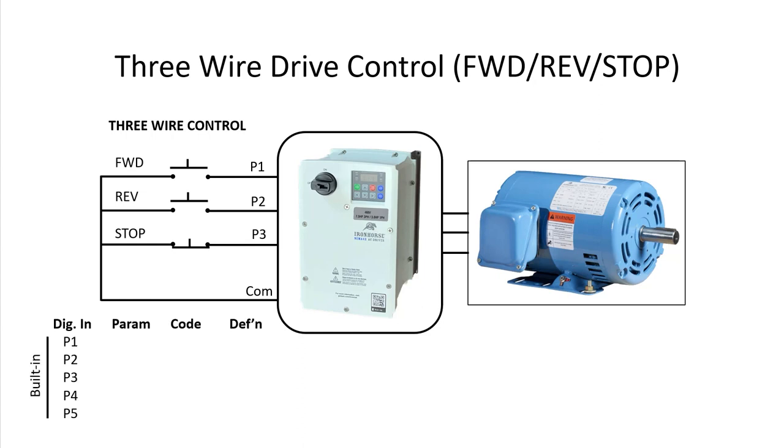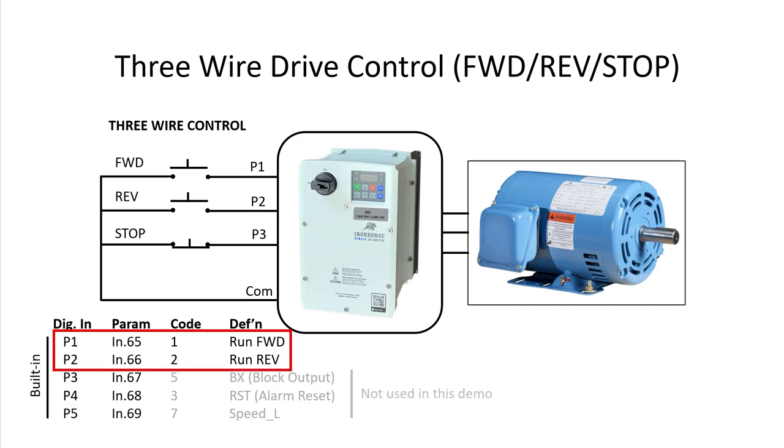These are the built-in digital inputs that come with the drive, the parameters used to configure them, and the default values. Using terminal P1 and P2 to control the direction is exactly what we want, so no change is needed there. And we'll use digital input P3 which defaults to an output inhibit for the stop button which is code 14.